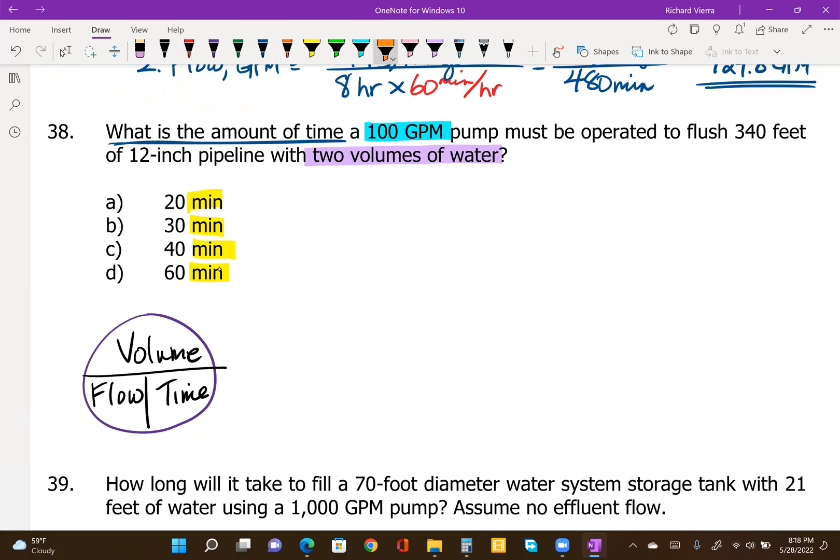So it is going to be calculated as volume over flow. Time in minutes is what we get when we take a volume of water in gallons and divide by a flow rate in gallons per minute. We do know the flow, 100 gallons a minute, but what we don't know is the volume amount that is going to be required to flush this line through twice. So this is what we have to find first before we can do the time calculation.